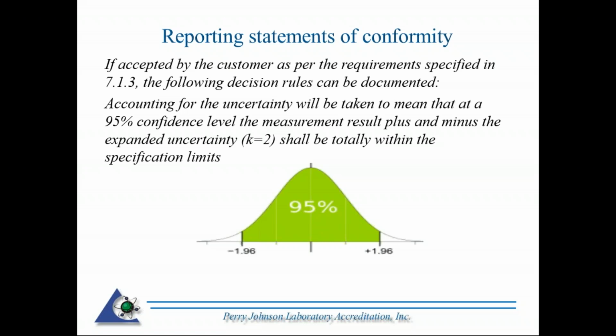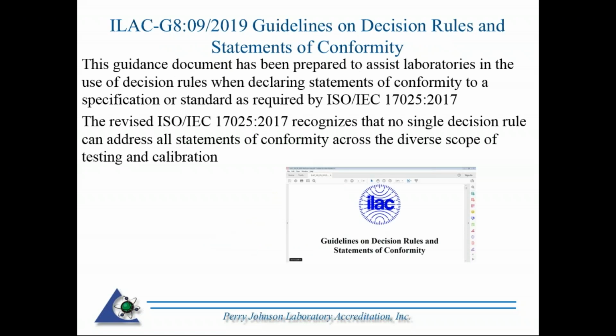So you have to, and I'm going to talk about a guidance document here that ILAC just released not too long ago, you wouldn't say pass, fail, in tolerance, out of tolerance. ILAC coins the phrase conditional pass, conditional fail. PJLA currently in PL3, we actually have the term pass indeterminate, fail indeterminate, under those conditions where measurement uncertainty may actually affect the statement of compliance. So there's the ILAC document that I was referring to. It's just a guidance document. It came out a couple months ago, and I was able to utilize it in the PJLA webinar a couple months ago. So I did go through some information within the ILAC G8 document, which is the guidance on decision rules and statements of conformity.